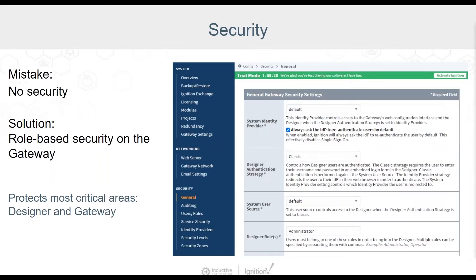Let's talk about gateway security first. The primary purpose of gateway security is to protect access to the two most critical areas of Ignition: your Designer and your gateway. The majority of gateway security settings can be found on the gateway general security settings page — look for the link in the config section under Security. By default, only an admin user can access the configuration page, status page, or the Designer, so you have some security in place already. You can make additional changes here.